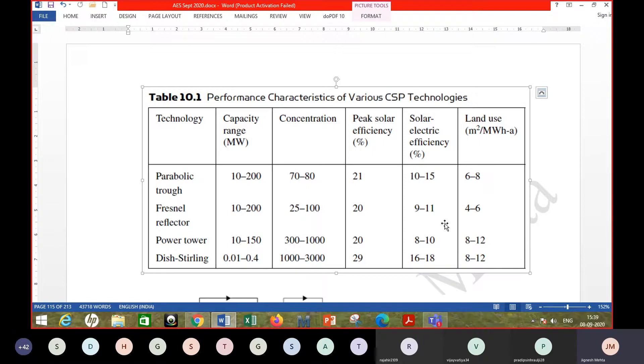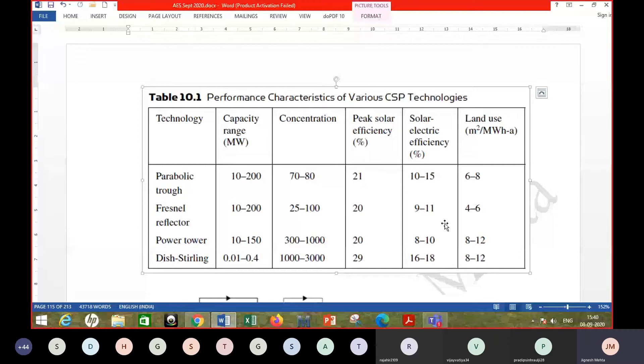One option is the parabolic trough type collector, used in power plants ranging from 10 to 200 megawatts. The concentration ratio is generally not very high — up to 70 or 80. Peak solar efficiency is around 21% and solar electric efficiency is 10 to 15%. Land use is an important factor; parabolic troughs consume around 6 to 8 square meters per megawatt-hour of annual power production — not the lowest, but among the lowest. The Fresnel lens collector has the lowest land use value.